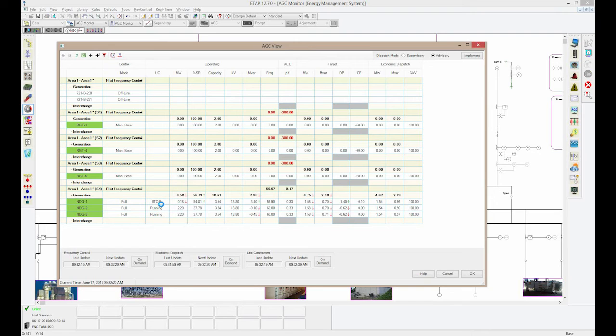So by controlling when you start and stop the generators, you can have some measure of fuel cost savings, especially in microgrid scenarios in remote locations where it's very expensive to bring fuel, such as islands or forward military bases and transportation, such as marine systems.